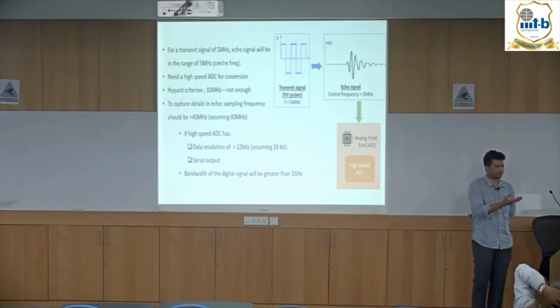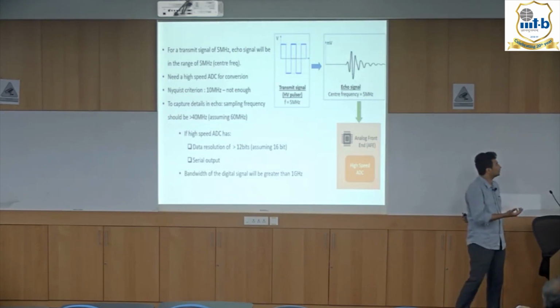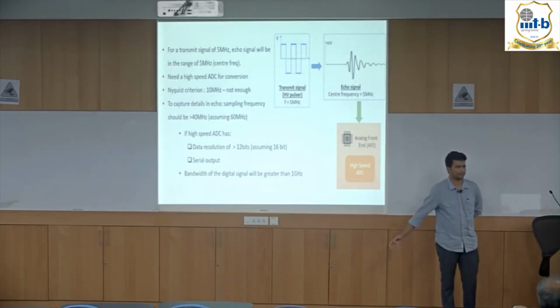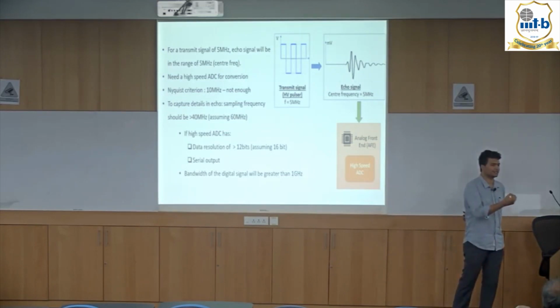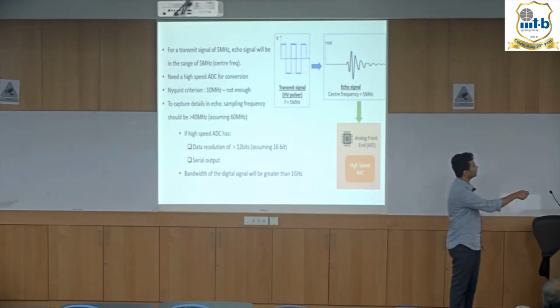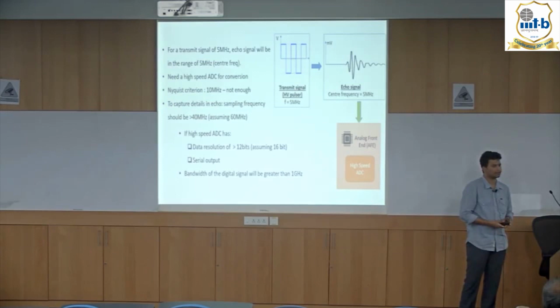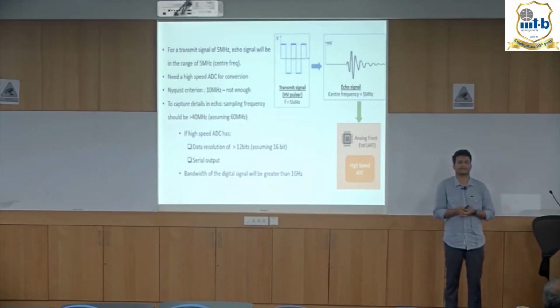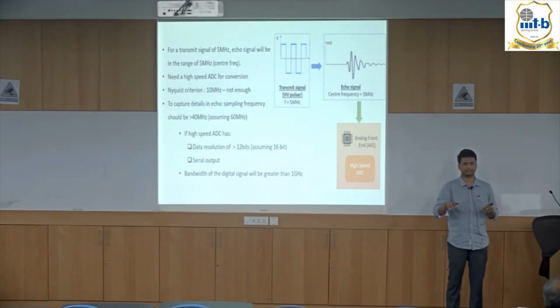According to Nyquist criteria, we need a 10 megahertz sampling rate. But to get the details of the echo, to capture the variations along the curves of the echo, we usually sample it at a higher rate, 40 or 60 megahertz. And if the ADC has a resolution of 16 bits and we are serializing the whole data, then the bandwidth of the output digital signal reaches around 1 gigahertz.